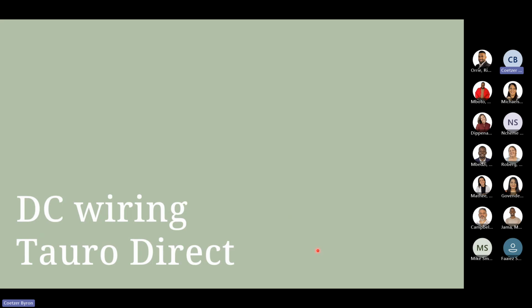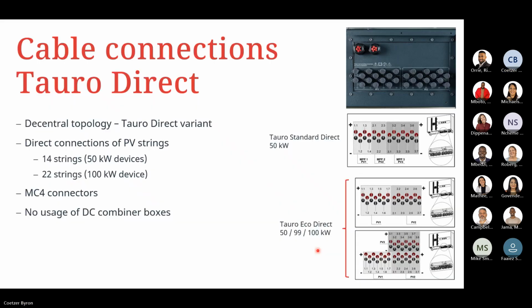If we are wiring up the DC wiring of the Tauro direct variant, this is the decentralized topology, the Fronius direct variant. When you are ordering your Fronius Tauro, you'll see it'll either state 100D or P. This refers to either the direct or pre-combined variant. On the direct connections of your PV strings coming in, on the 50 kilowatt devices, we have 14 strings in total, split by 7 and 7. And on the 100 kilowatt variant, we've got 22 strings in total on the unit, so it'll typically split by 7, 7, and 8, for example. And again, no usage of DC combiner boxes.